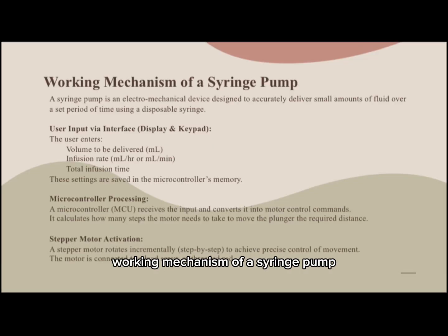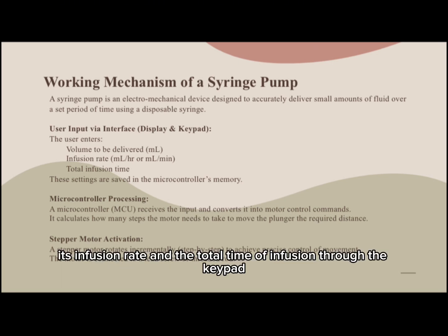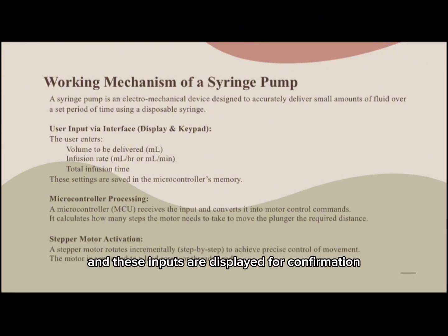Working mechanism of a syringe pump: first, the user inputs are entered, which typically include the volume to be infused, its infusion rate, and the total time of infusion through the keypad, and these inputs are displayed for confirmation.